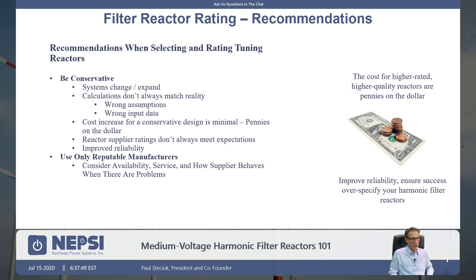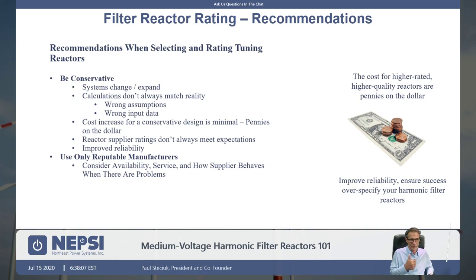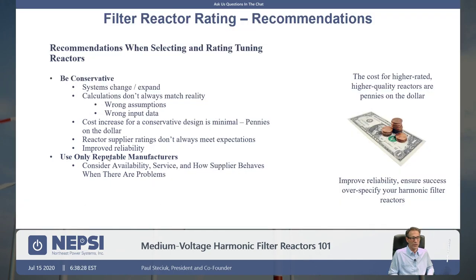These reactors can be enormous — sometimes enclosures are designed around the reactors. If you've under-specified a reactor and later determine it's undersized, the larger replacement reactor may not fit inside the enclosure. It's important to over-specify the reactor current ratings, both from a harmonic standpoint and from the fundamental standpoint — it's going to improve reliability. Also consider using only reputable manufacturers. NEPSI uses only two US manufacturers and one in Europe. They should be manufacturers very well aware of harmonic filter reactor design who have done it many many times.